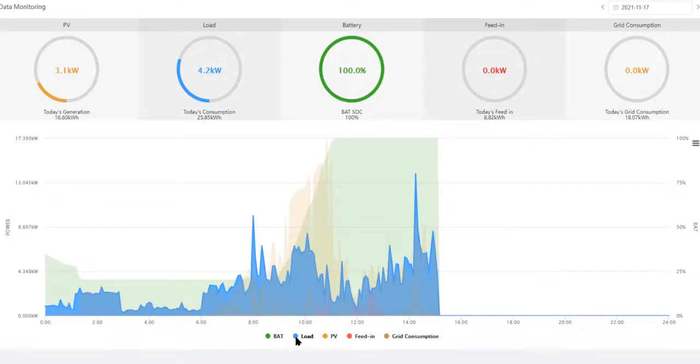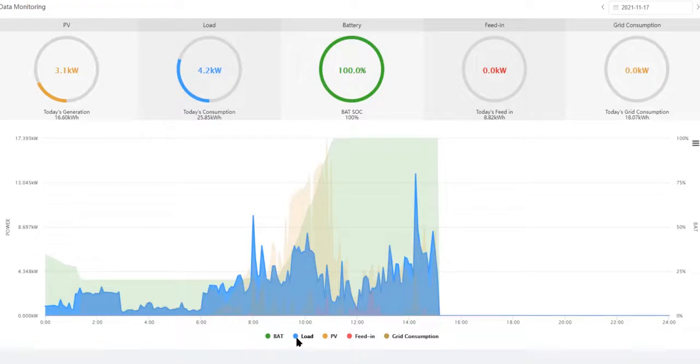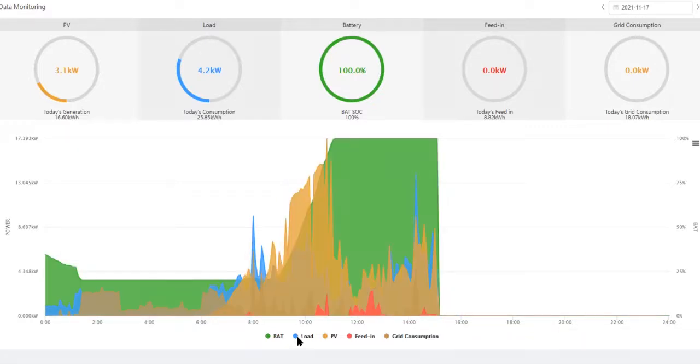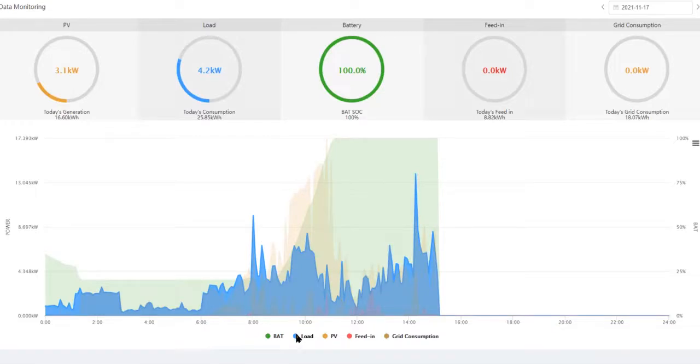So the important thing to understand, then, is that when we are talking about export here, we are not talking about the special situation that happens in a power cut. Then we have another function that's not letting electricity go out to the grid at all. So that's a safety feature when there is a power cut, but that is a completely different function. It's important not to confuse these two functions. They are completely different.